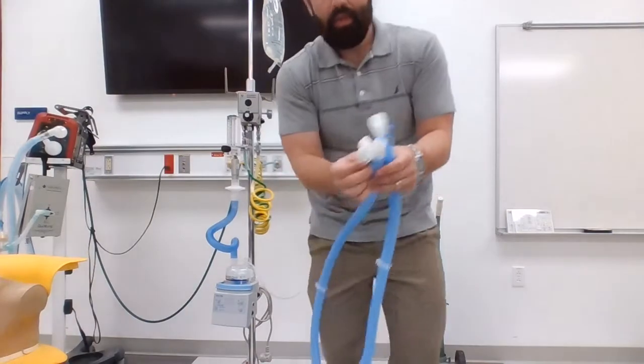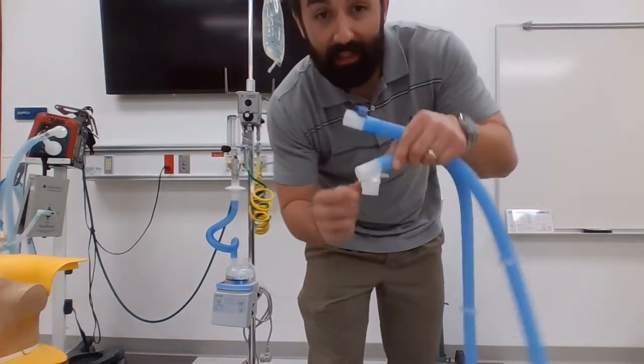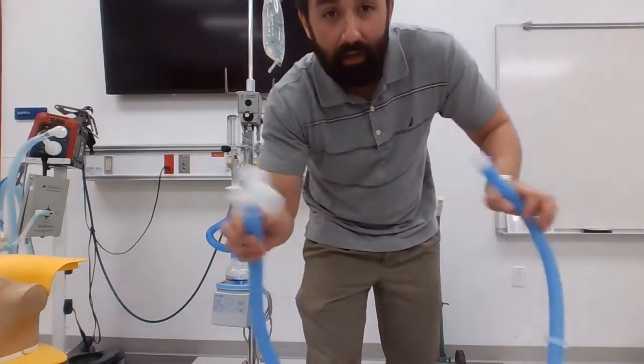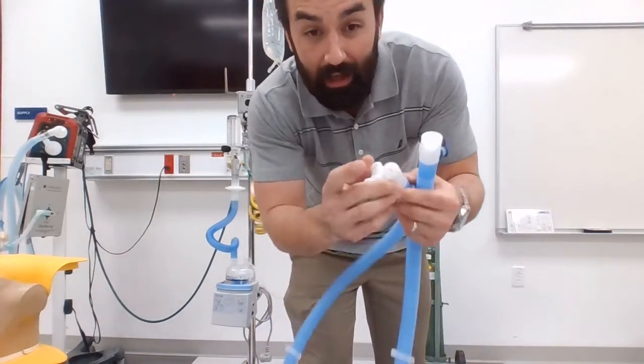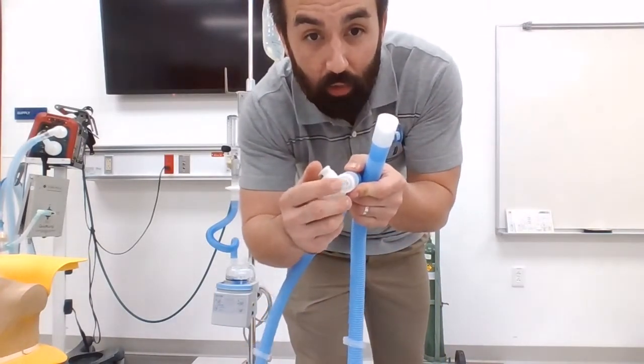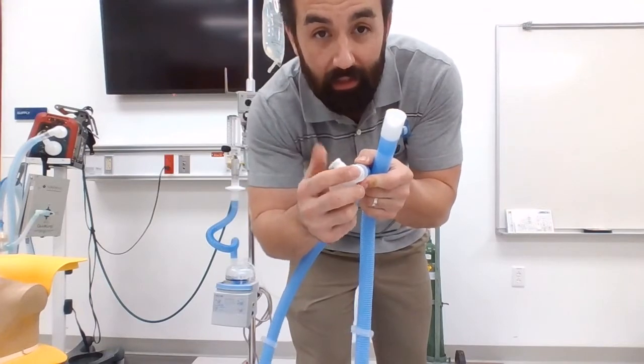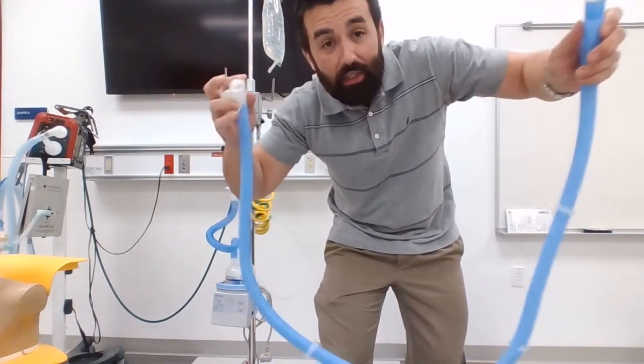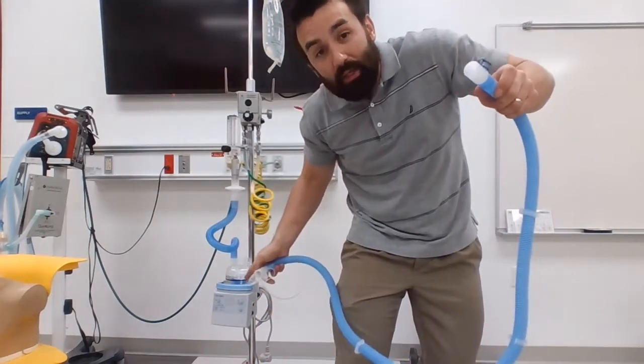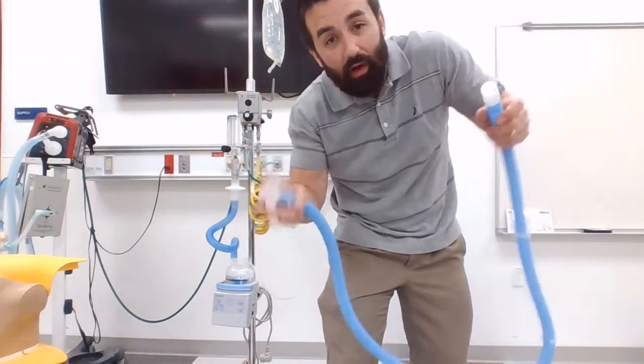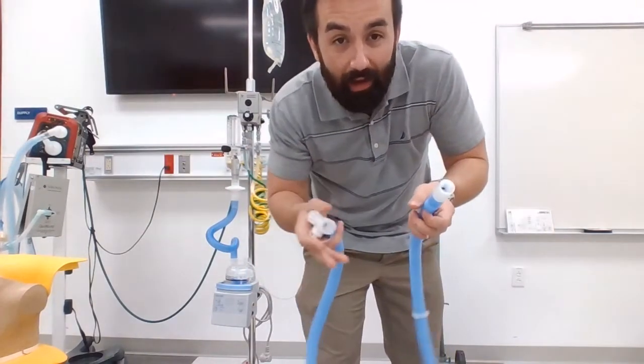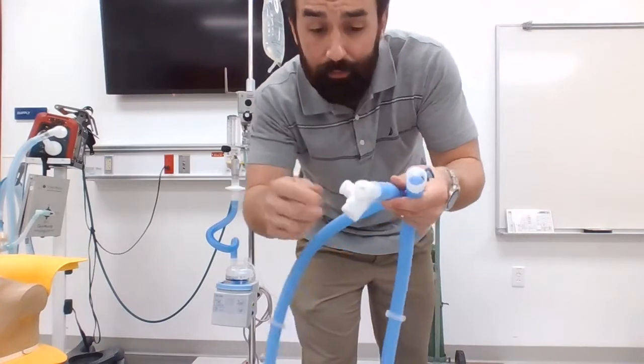What we have on this side is going to clip onto the top of the passover. I've got a spot where I'll hook up electrical charge on the back side of this circuit to energize and heat it, so my passover gets that gas conditioned to 100% saturation at 37 degrees Celsius, or body temperature.